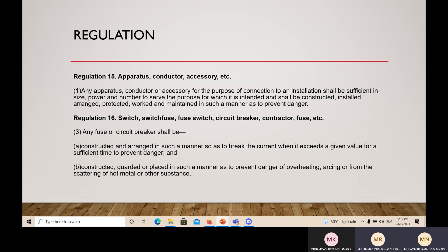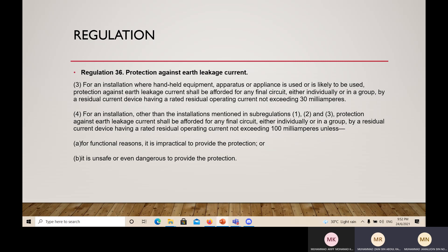Regulation 36 — Protection against earth leakage current. For installations where handheld equipment or apparatus is used or is likely to be used, protection against earth leakage current shall be afforded for any final circuit, either individual or in a group, by a residual current device having a rated residual operating current not exceeding 30 mA. For other installations not mentioned in subregulations 1, 2, and 3, protection shall be afforded by a residual current device with rated residual operating current not exceeding 100 milliamperes, unless for functional reasons it is impractical or unsafe or dangerous to provide the protection.